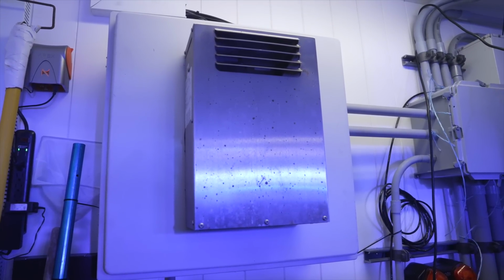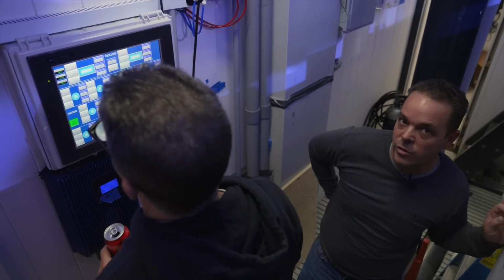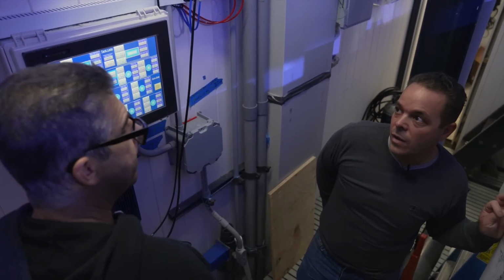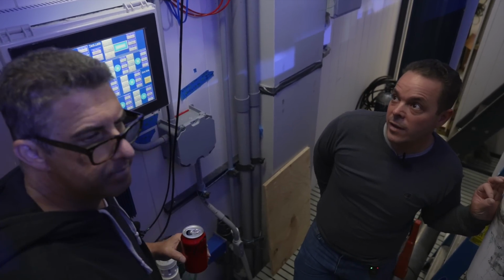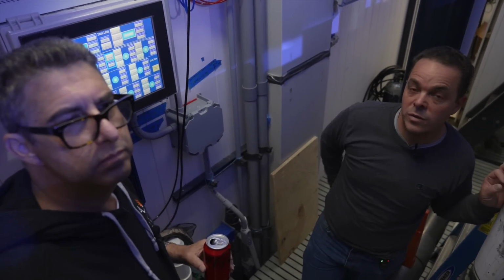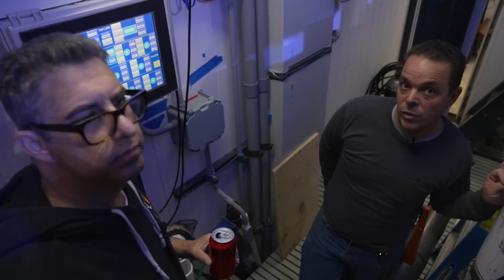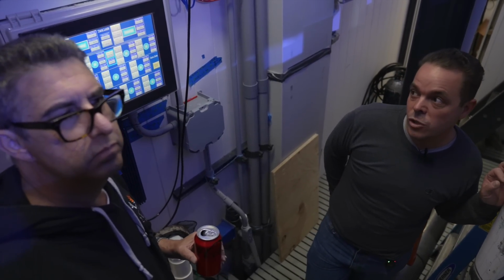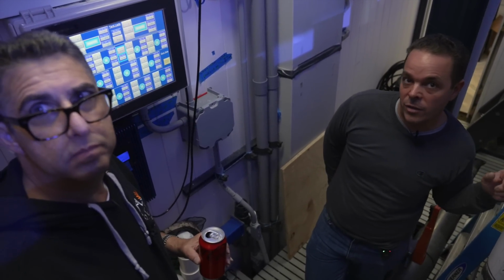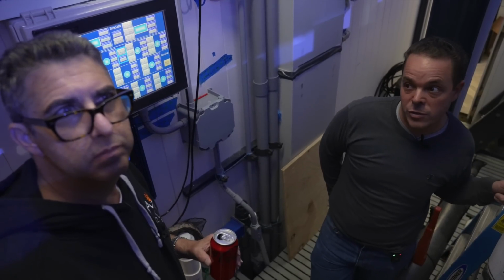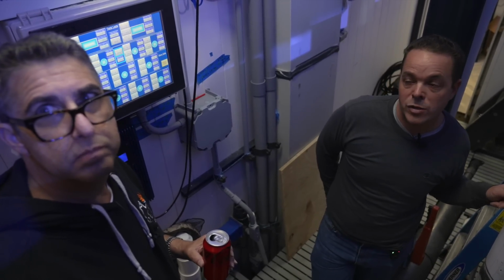So they're currently running at 98, 92 to 100. And we have a fail-safe that if one of these heat exchangers was to fail and the ballast enclosure was to get too hot, the computer would shut down that bank of ballast and alert us that we have an over temperature situation, so we don't damage the ballast.